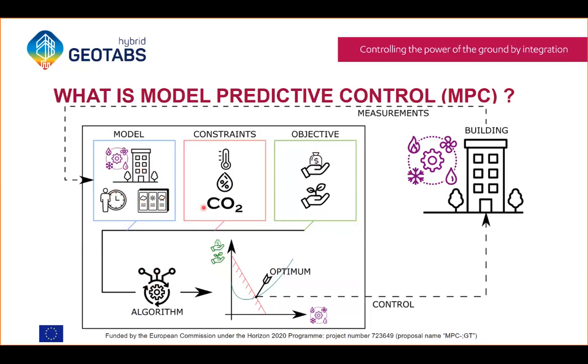The second block is constraints, which need to be respected at all times. For example, comfort constraints such as temperature within bounds, relative humidity, and CO2 concentration. Finally, there is a block which is the objective, the quantification of what needs to be optimized. It can be minimizing operational cost, optimizing sustainability, maximizing comfort, or finding a trade-off between these things.